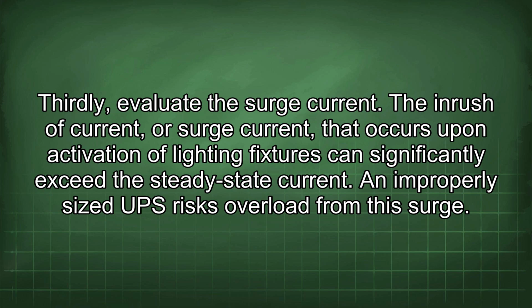Thirdly, evaluate the surge current. The inrush of current, or surge current, that occurs upon activation of lighting fixtures can significantly exceed the steady-state current. An improperly sized UPS risks overload from this surge.